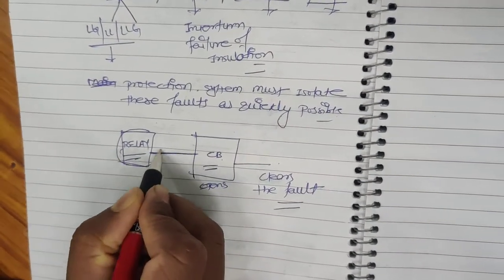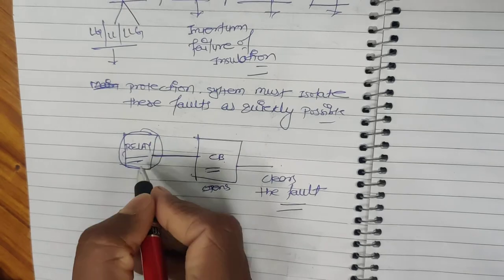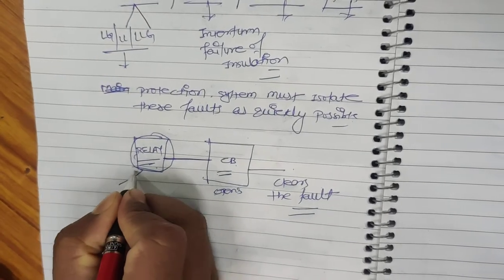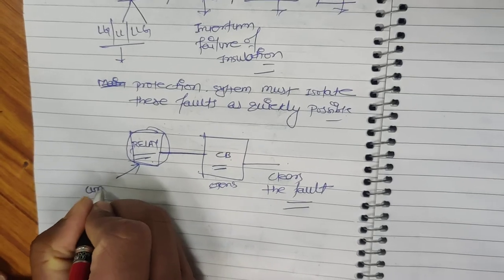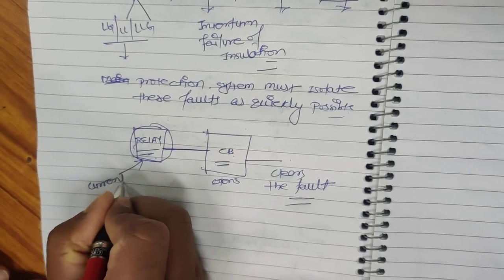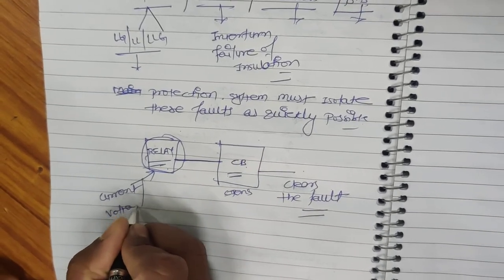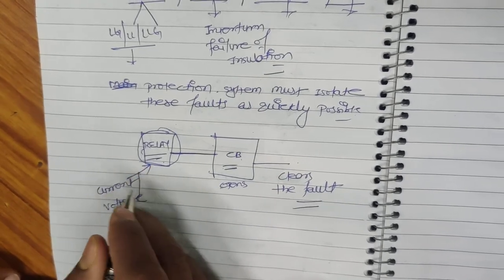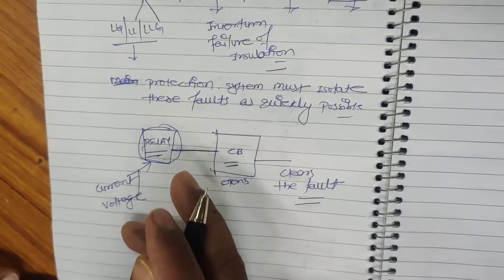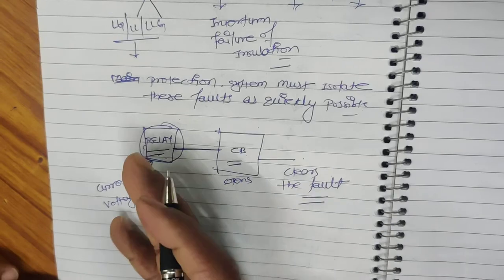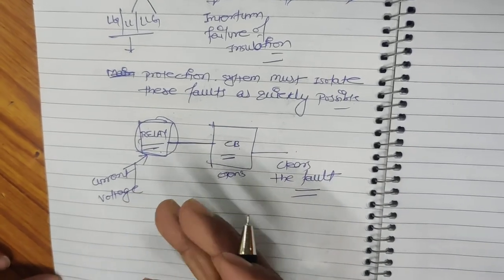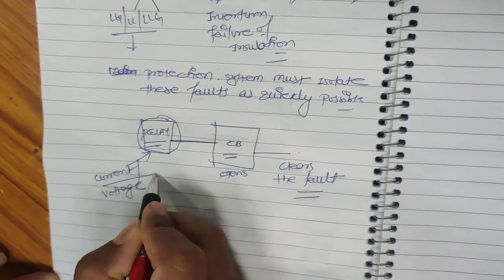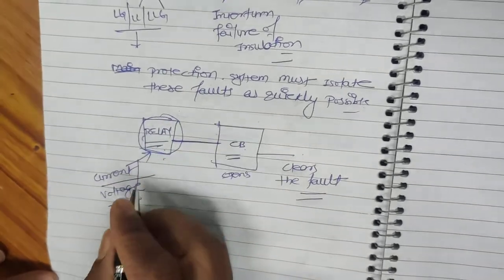The relay determines the fault on the basis of its algorithm. This algorithm may be based on current, voltage, or any combination of current and voltage — such as the ratio of voltage to current to form impedance, admittance, power factor, or power angle. There may be many different types of algorithms inside the relay.